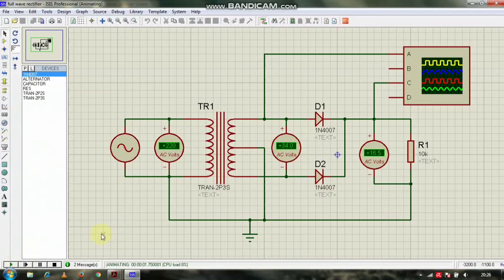Now you can see the input is 220 volt AC, and the voltage from the transformer secondary measured between the two terminals is 34 volts. This is basically the RMS value. It should come out to be 24, but since the meter shows RMS value, it is showing 34. We will verify whether it is actually 24 volts or not, and the output load AC voltage is coming out to be 16.5 volts.